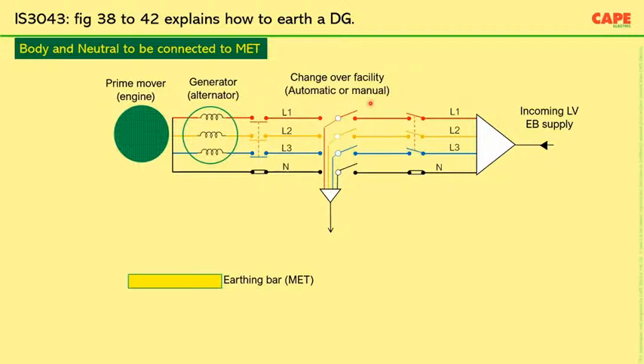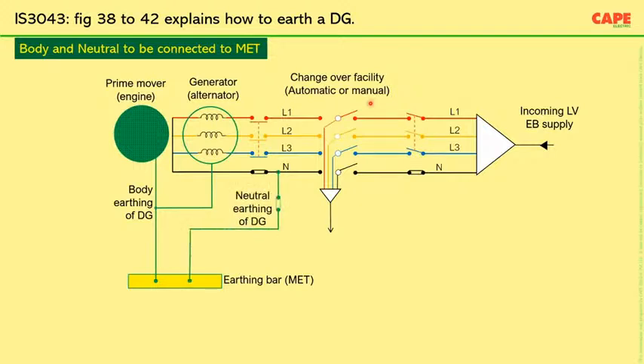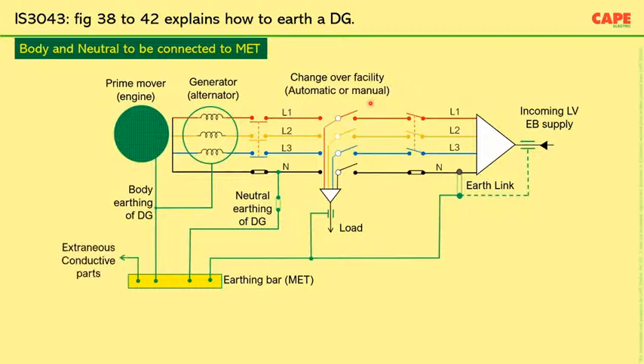First you have the earthing bus bar. What I am showing in the picture is the correct way of earthing in a typical building. You have the earthing bus bar, the DG body and the neutral, the body, the alternator and the engine connected to the earth bus bar. The neutral is connected to the earth bus bar. The incoming electricity board supply, the PE conductor, the protective earth conductor, is also connected to the earthing bar. Now the load side PE conductor, the protective earth conductor, is connected to the earthing bar. And now you see this extraneous conductive part. Say for example, you have a lightning protection system.